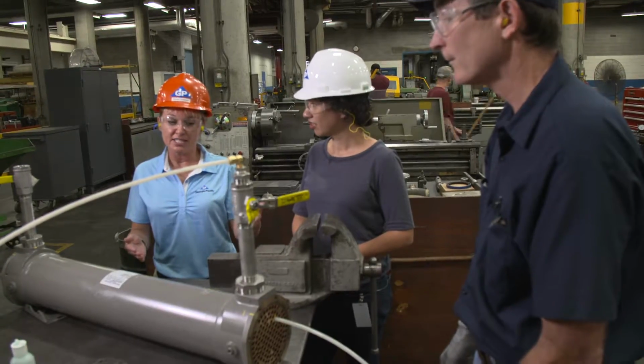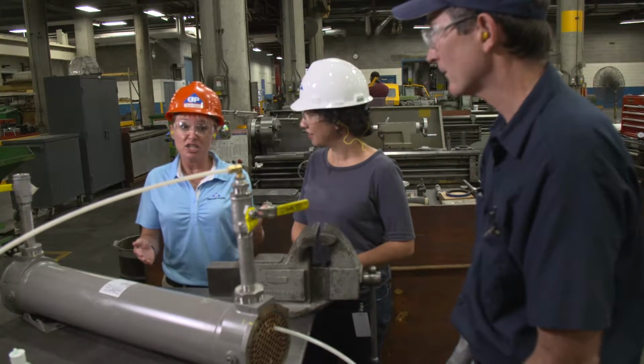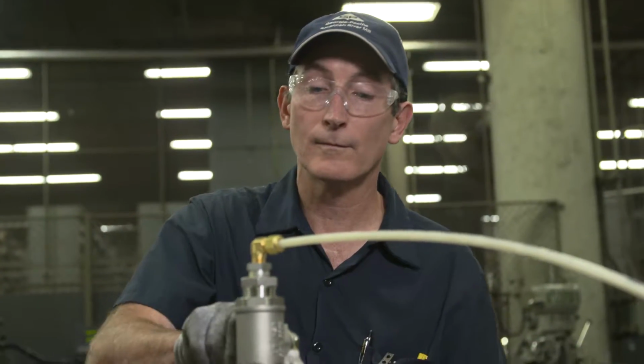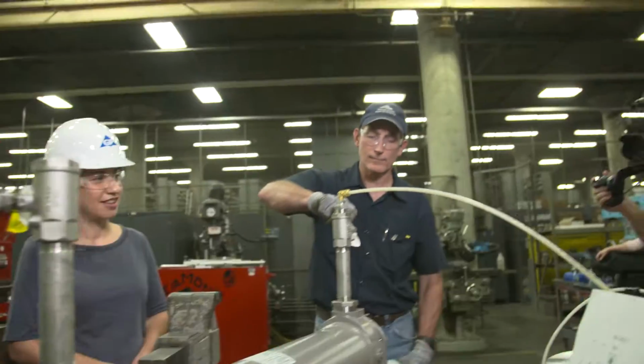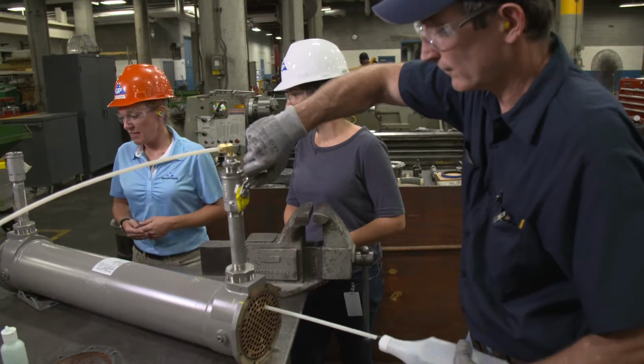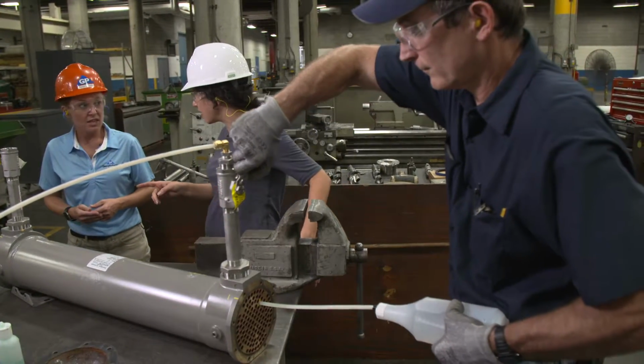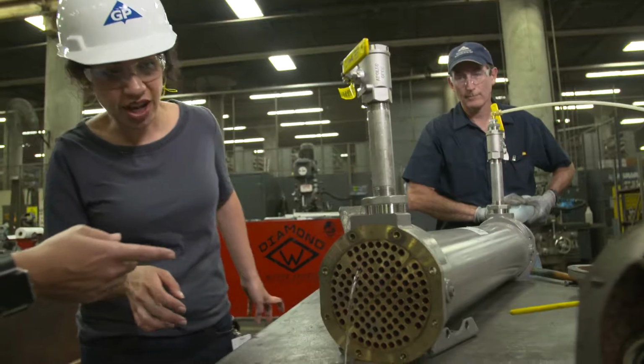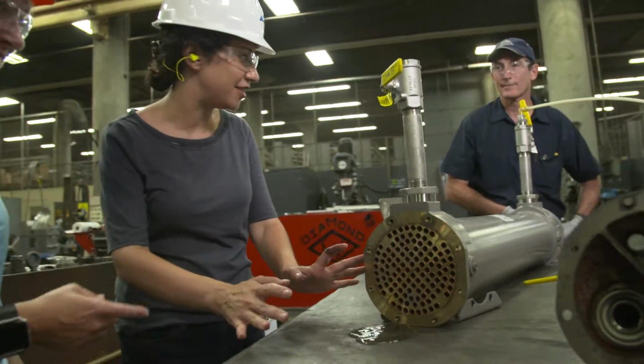So we now have the heat exchanger set up for a shell side test so we can test for a leak on the tube side. Kenny's going to apply pressure by opening the valve to the shell side, giving us water supply, and then we'll look at the end. If water comes out, it means we have a leak. Exactly. So we... oh my gosh, and we do. Wow, how do we stop that?